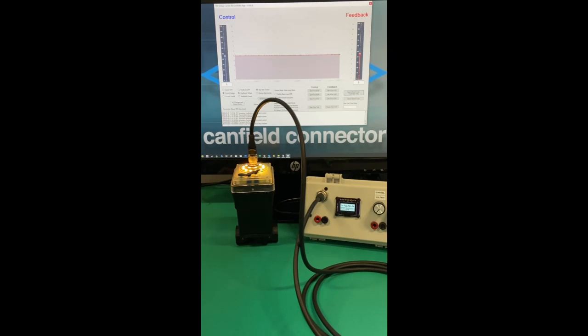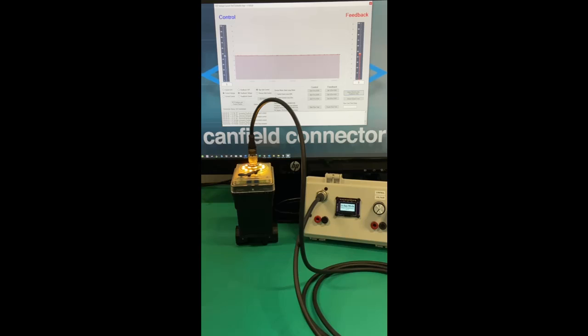Modifying the speed pot or the dither pot will change how quickly the stepper valve reacts to the differences between the control and the feedback inputs. A lower setting of the speed pot will mean that the stepper valve will open slower. A lower setting of the dither or hysteresis pot will make the stepper more responsive when there is a smaller difference between the control and feedback signals.